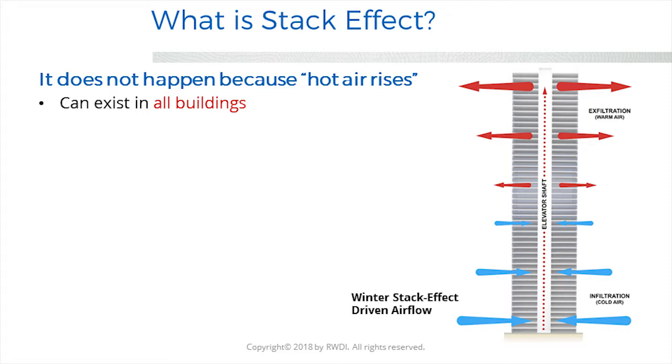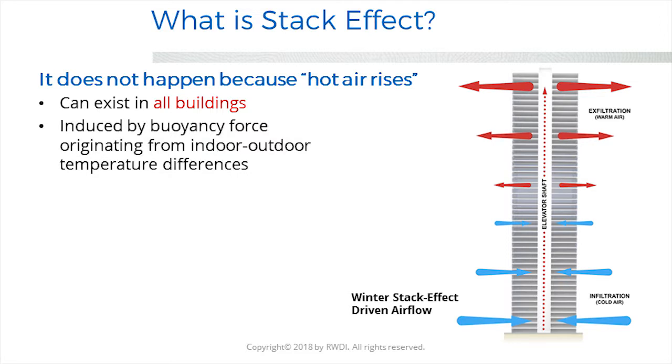Hot air does rise, I'm not denying that, but the reason why stack effect gets set up is because the air inside the building is lighter than the air outside the building. So the column of air inside the building weighs less. And I'll come back to that in a few moments with an example. But this buoyancy force is generated by the indoor-outdoor temperature difference. The image that you see here is for winter mode.